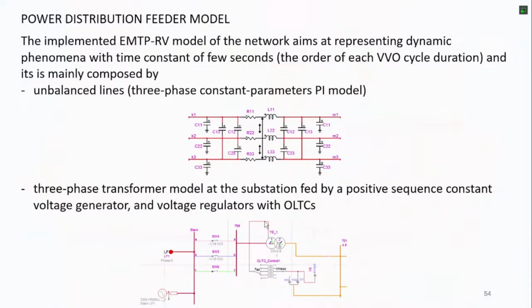One of the aims of this secondary voltage regulator is to limit the change in the tap of the transformer, because the more frequent the change of the tap, the shorter the life of the transformer. So there is the maintenance. So we need to decrease the number of changes.